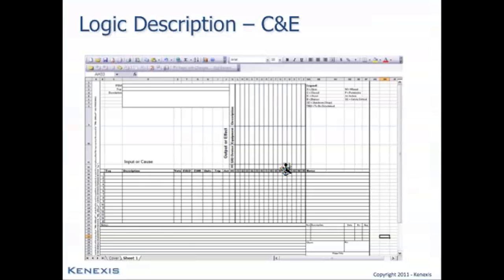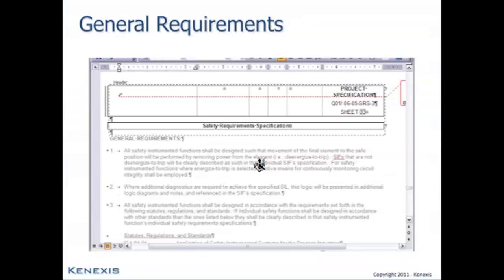Okay, this slide shows you a typical example of what we would expect in a cause and effect diagram, with inputs on the rows and effects on the columns. And in addition to the tag names, other information including engineering units, trip points, delays, whether or not the inputs and outputs are safety critical, and drawing numbers that the instrumentation is included on. These are all common attributes of cause and effect diagrams for logic description. General requirements and detailed notes, as mentioned previously, are plain text and typically are simply listed in a numerical fashion in a word processing document.